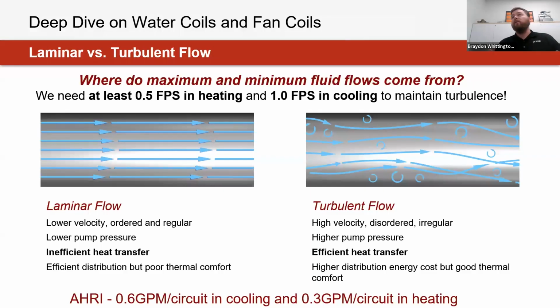And what that actually equates to, normally it's listed as velocity, but I've converted it over to GPM, just as that's a little bit easier to digest. That equates to 0.6 GPM per circuit for cooling and 0.3 GPM per circuit for heating.